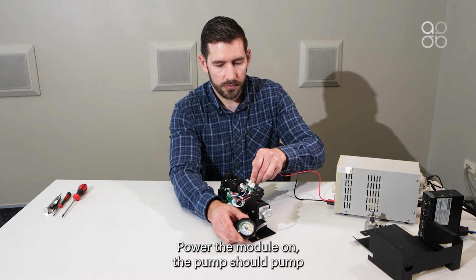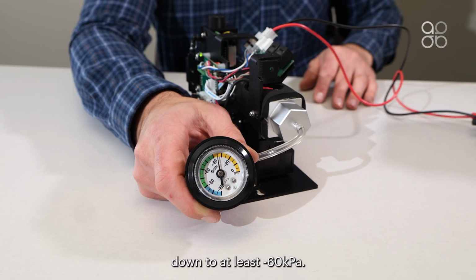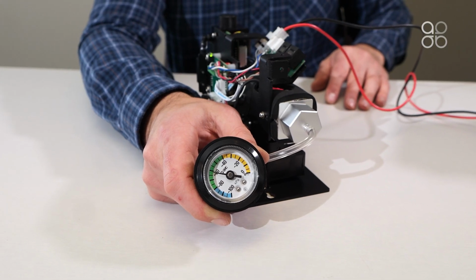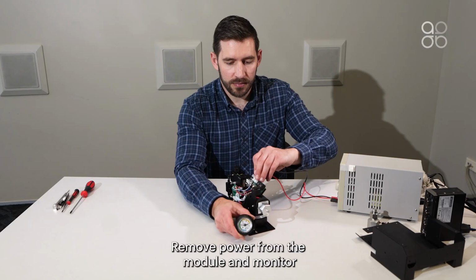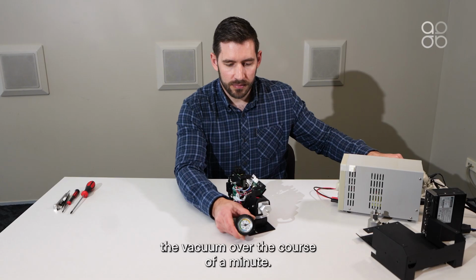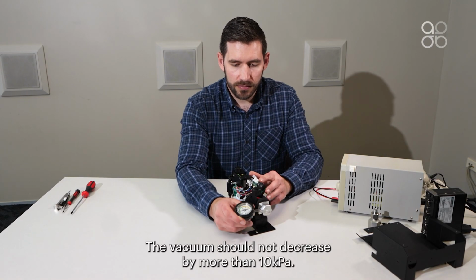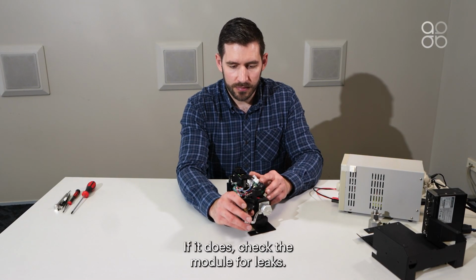Power the module on. The pump should pump down to at least minus 60 kPa. Remove power from the module and monitor the vacuum over the course of a minute. The vacuum should not decrease by more than 10 kPa. If it does, check the module for leaks.